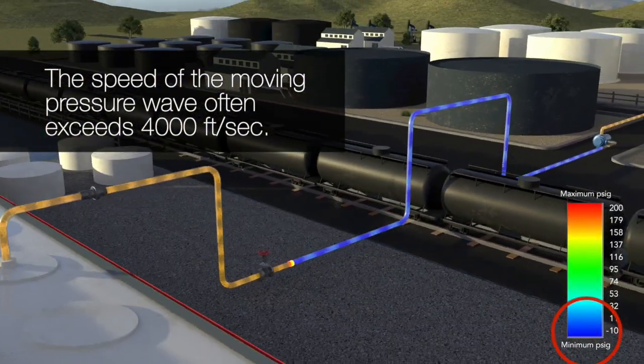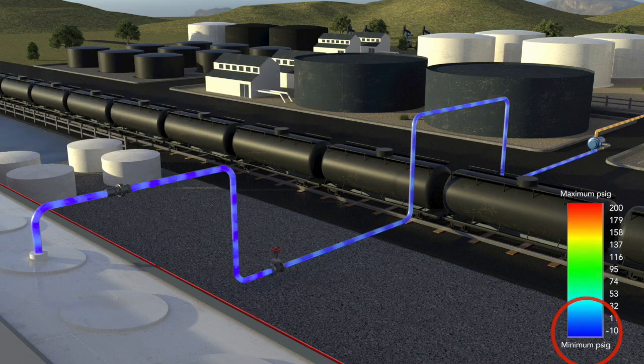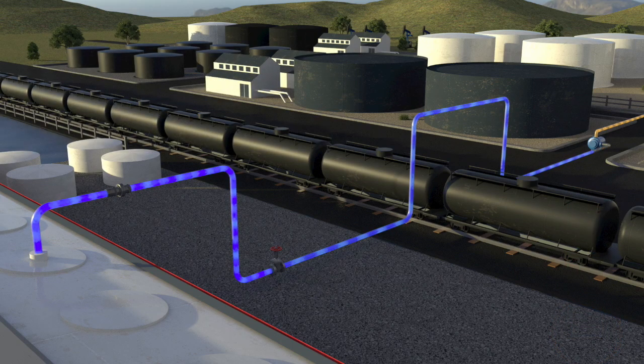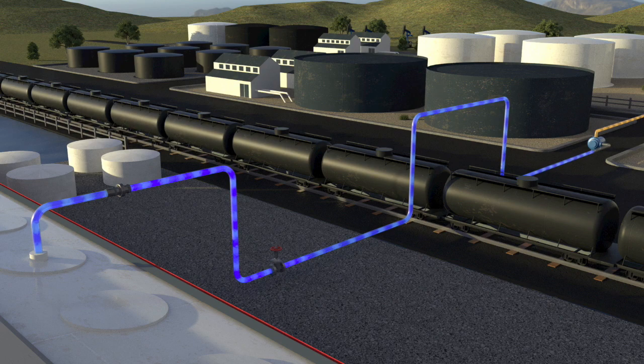When a low-pressure transient wave reaches the end of the system, it is reflected backwards with enough energy to collapse any vapor pockets that have formed.